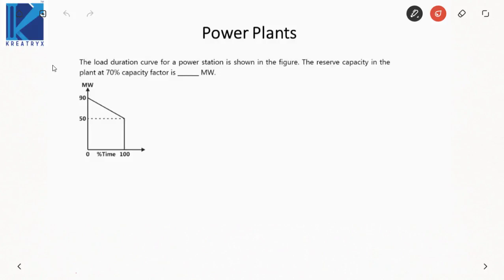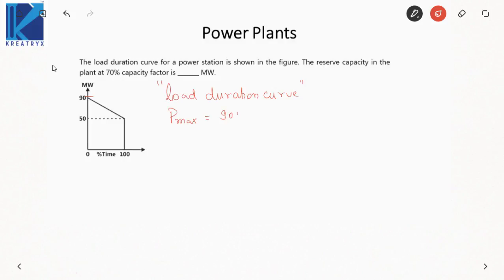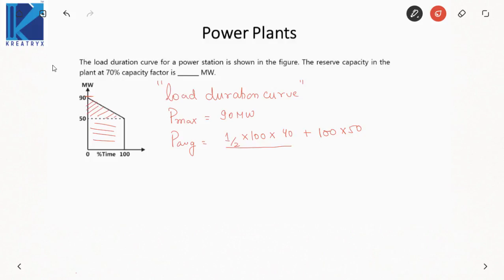In the next problem, we are given a load duration curve for a power station and asked to find the reserve capacity for a 70% capacity factor. From the load duration curve, the maximum demand is 90 megawatts. The average demand can be found as area divided by duration. Since the curve is a straight-line variation, the average is maximum plus minimum divided by 2, which is 90 plus 50 divided by 2, giving 70 megawatts. Remember, this shortcut only works when the curve is a straight line.